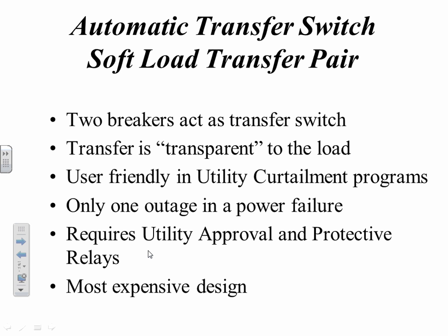One last type that I include in the presentation is what we call a soft load transfer pair. It is an automatic transfer switch, but instead of a contactor, we're actually going to use two breakers that act as a switch. The operation of this switch is transparent to the load, which I'll explain why in a minute. It's very user-friendly in utility curtailment programs, and I'll tell you a little bit about what those are.